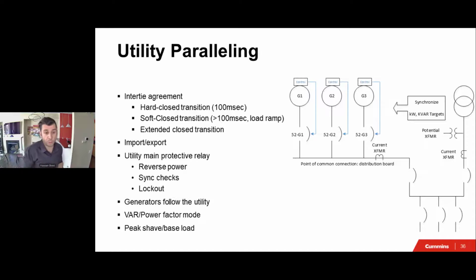And then there's extended, where you can be connected for days with the utility, obviously for demand response and financial incentives, right? When it comes to paralleling with the utility, it's the same thing. Those genset controls, all we're doing is controlling the fuel and the excitation. And all we need is just one synchronizer that tells the set points for those generator sets to match the utility. We cannot control the utility. The utility is considered an infinite source. Even if we connect hundreds of generators, the utility will be much bigger. I guess it varies depending on the utility, but typically they're considered an infinite source.